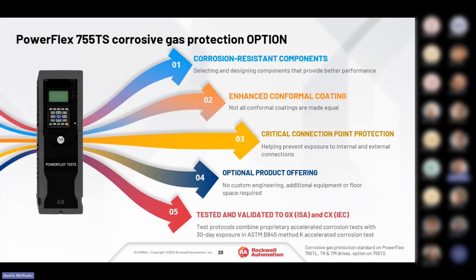Enhanced conformal coating. So not all conformal coatings are made equal. Our VFD 750 series boards do come standard with conformal coating, but the enhanced conformal coating really extends the life of our components from a corrosive perspective. I'll show you a picture of two boards, one that has standard conformal coating and one that has XT conformal coating, and you can see the difference with the dendrite growths. Those are growths that can cause havoc and shorts on our components. And this is tested and validated.